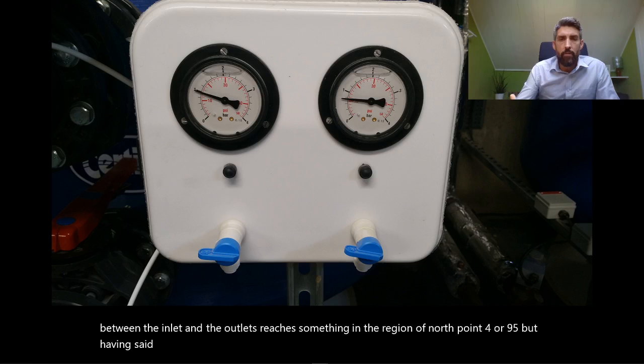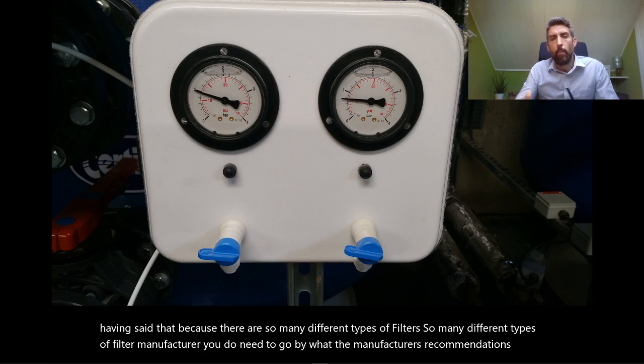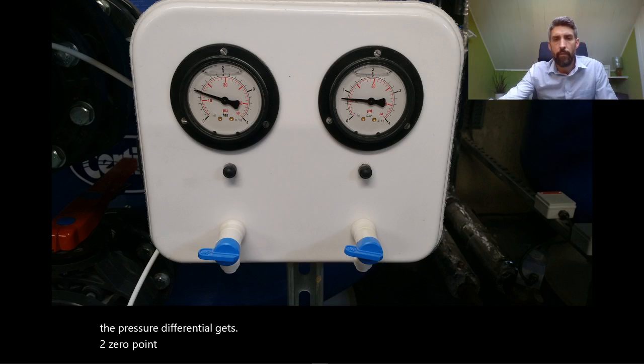Having said that, because there are so many different types of filters and filter manufacturers, you do need to go by what the manufacturer's recommendations are. But a general ballpark figure for commercial swimming pool filters is to backwash when the pressure differential gets to within the 0.4 to 0.5 range.